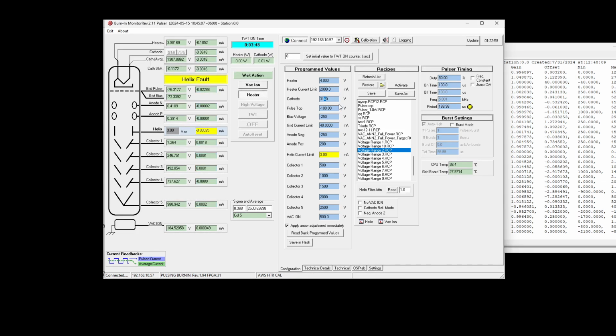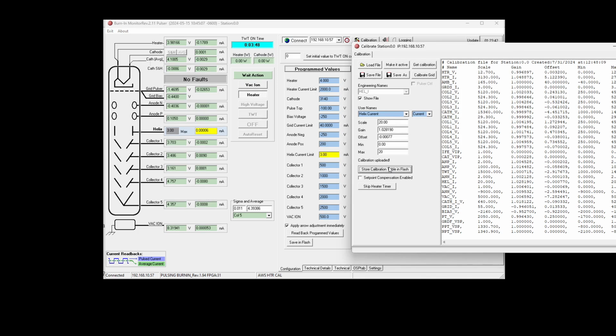5, and at 2.26 we tripped with a trip level of 3, which I consider adequate. So we've tested the trip functionality of the Helix at multiple trip points. We can now assume that this is calibrated. We care more that this reading is accurate to the meter, as long as the actual current at which it trips does not exceed 3 milliamps or 4 milliamps or whatever the set point is that we've set. And that's how to calibrate Helix. So we'll just hit this store calibration table in Flash, and we're done.